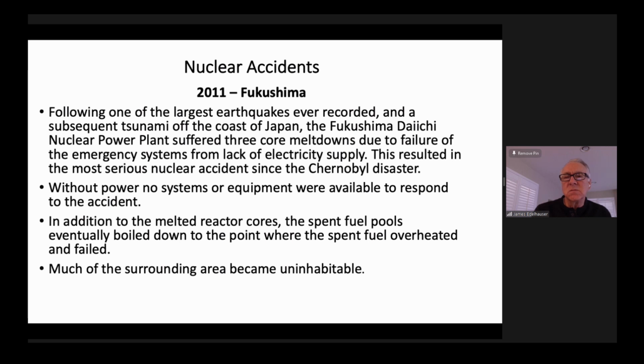Just from the tsunami alone, it was devastating to the area. It wiped out all power sources to the plant — knocked down all the transmission lines, flooded the standby diesel generators, and flooded the electrical distribution system. So they were sitting there in the dark with no power. Despite all the backup systems in their designs, those systems required power to operate and keep the reactor cores cool, and as a result they melted down the cores of 3 plants.